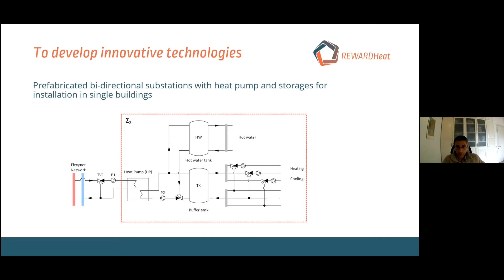The third barrier we encounter when addressing waste heat in district heating is that you have multiple energy sources feeding into the system - a big leap compared to conventional networks with only one central thermal system. You can't simply switch the main gas boiler or CHP unit on and off as you would normally. You need to operate and manage every single source and sink in the network properly, in a detailed and continuous way throughout the day.